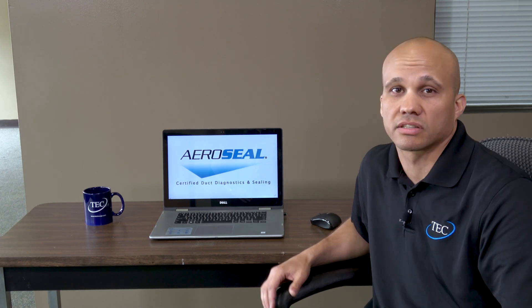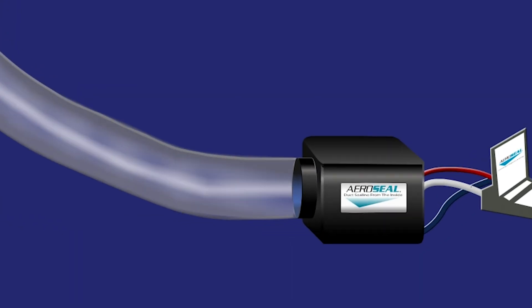The way this process works is we block off all the supply and return grills with foam blocks, we pressurize the duct with a high-pressure fan system, and then we inject glue in an aerosol form into the ductwork.